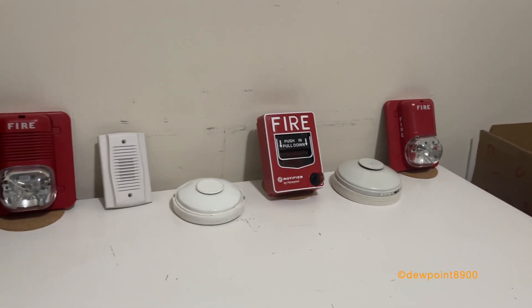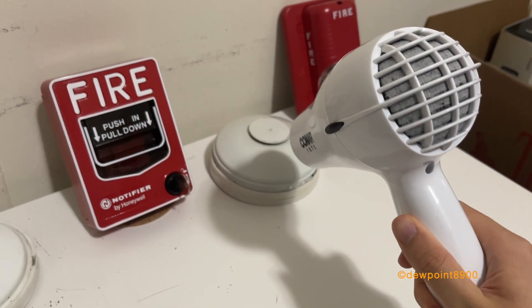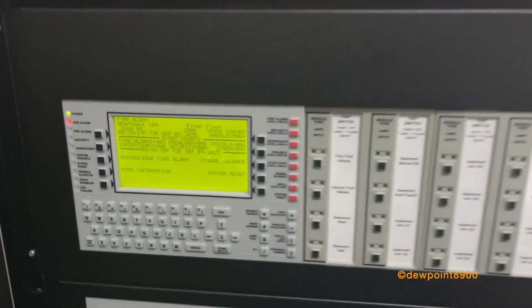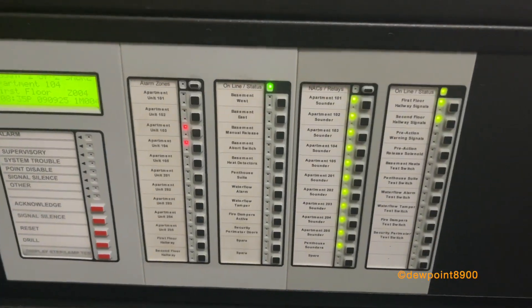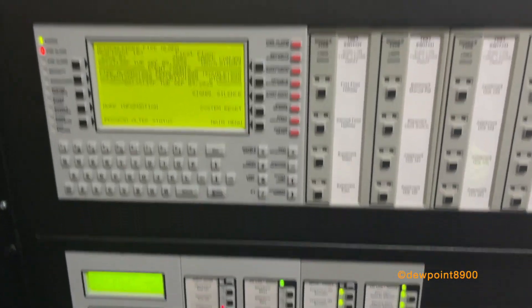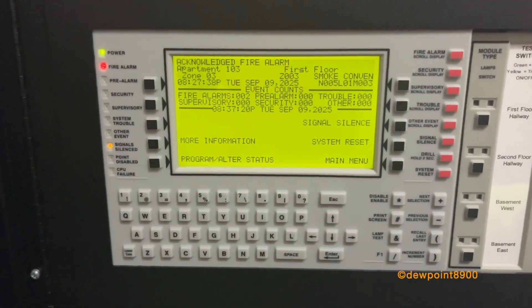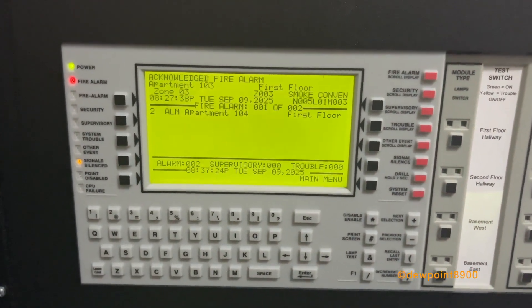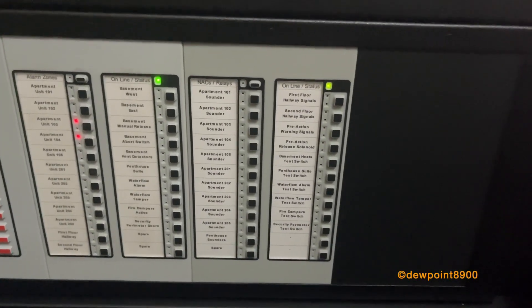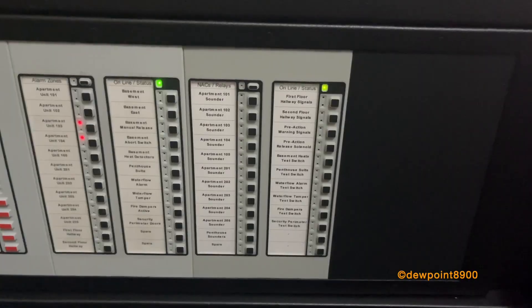Now let's activate the second heat detector, which will put the system into full alarm. If we check multiple events, there are now two alarms on the system. Apartment unit 104 is now indicating an alarm, also shown on the LCD-280 and the ACM-24AT. With the general alarm, the hallway signals — the Spectralert Classic — sounded, as well as every sounder in all the apartment units in the building, signaling a general evacuation of the entire complex.